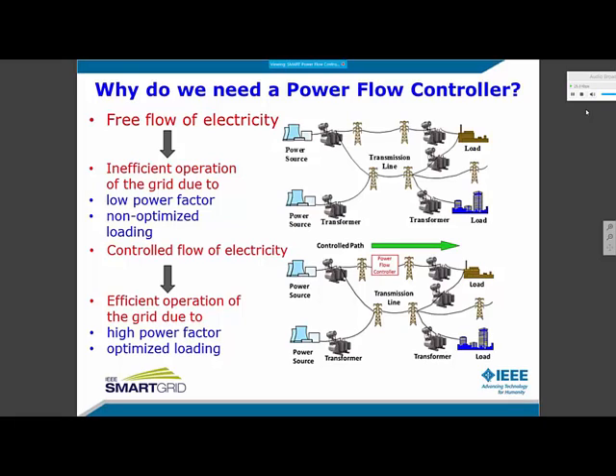Now back to the question, why do we need a power flow controller? Sometimes we need to increase the power flow through the desired transmission paths consisting of high voltage, low loss lines. Sometimes we need to decrease the power flow of a line to either redirect the desired transmission paths or to avoid a cascaded blackout if the line is tripped.